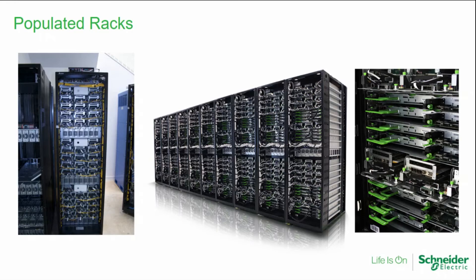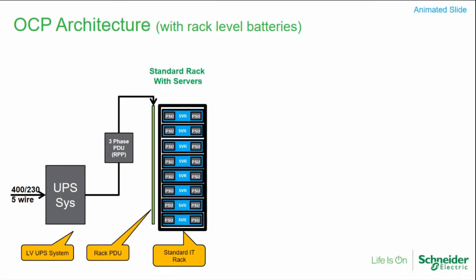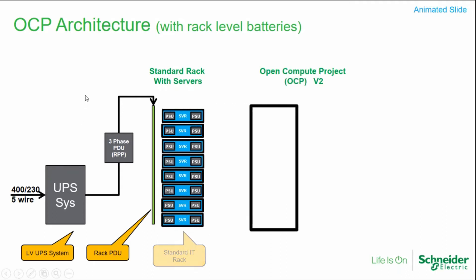Here's a slide showing what happens to the infrastructure just upstream of this rack. In a traditional data center, you'd have a UPS system, then a power distribution unit — PDU — or RPP (remote power panel), feeding a rack PDU or outlet strip in the rack, with cords going to each server which usually has two power supplies.